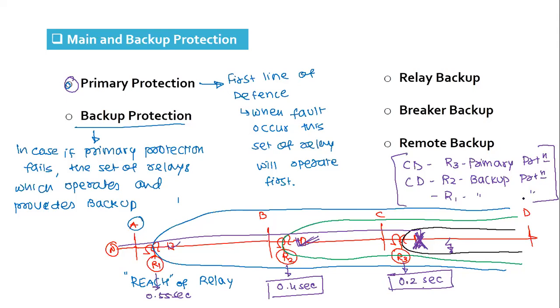That is what is called backup protection, primary and backup relay. Now I would like to ask you a question. If R2 relay operates in 0.2 second and R3 relay operates in 0.4 second for this fault, is it correct operation? No, sir.